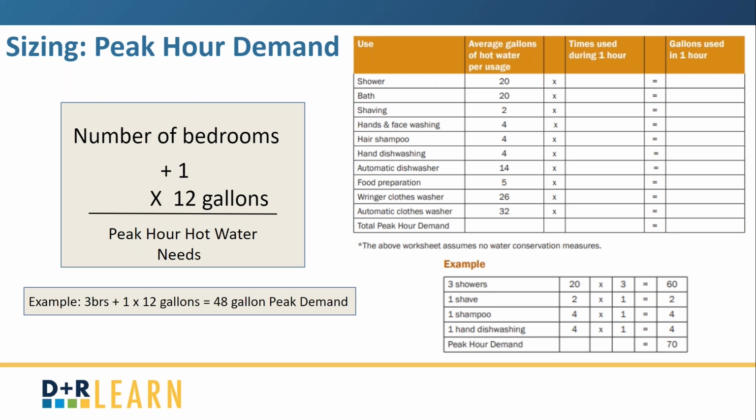So big point about sizing, and it's a big challenge, because the initial assumptions were that if you had a 50-gallon electric water heater or a 50-gallon gas water heater, you would replace it with a 50-gallon heat pump. No, you don't replace it with a 50-gallon. You go up one size and oftentimes two sizes.